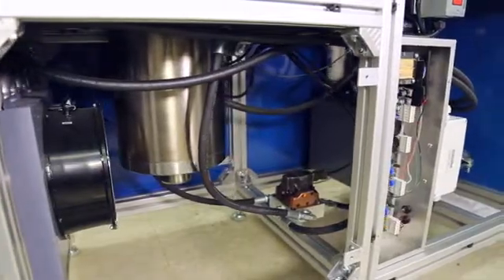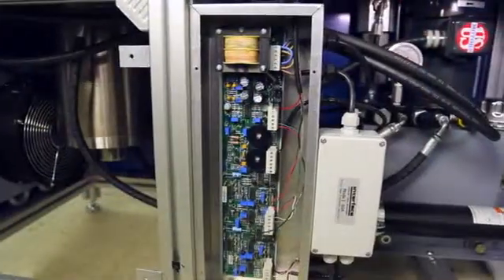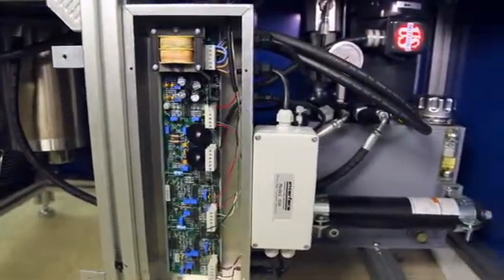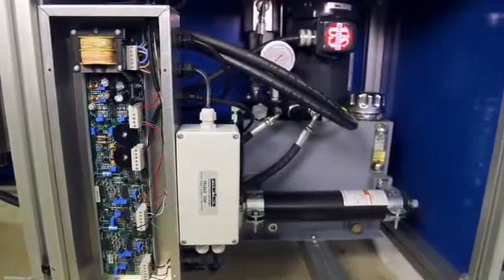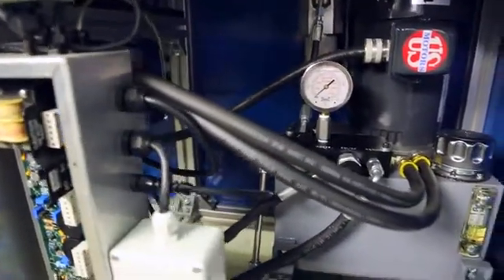Hydraulics in the Gold Standard Load Frame System include a 3,000 PSI hydraulic pump with a highly toleranced custom piston, providing low friction and long-life seals to minimize static friction.